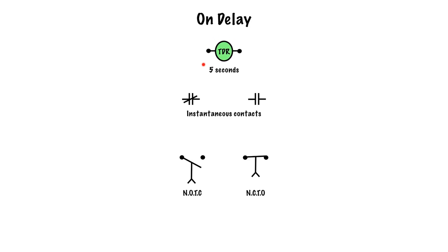So I've pushed a button and energized this TDR, time delay relay, which has a timing of 5 seconds. The moment I press that button, the instantaneous contacts respond immediately. The ones that were normally open become normally closed, and the ones that were normally closed become normally open. They don't pay attention to the time at all; they're just instantaneous.